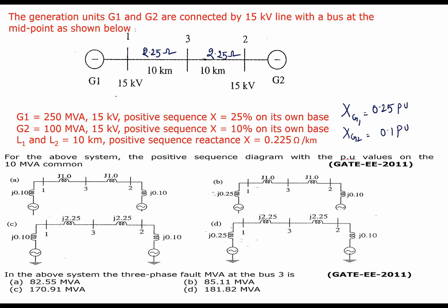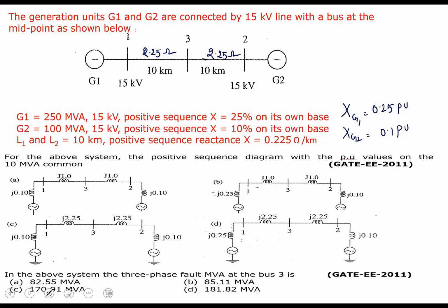Now you have to calculate the positive sequence diagram. Don't worry about the positive sequence term. Positive sequence means the power system is balanced. So far we have not entered into unbalanced analysis, so by default all the networks are positive sequence networks. Now find out the per unit values on a 100 MVA base. There is a print mistake. It is a 100 MVA common base. Okay, he did not mention the voltage base.